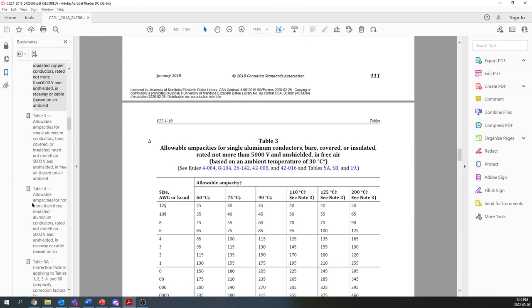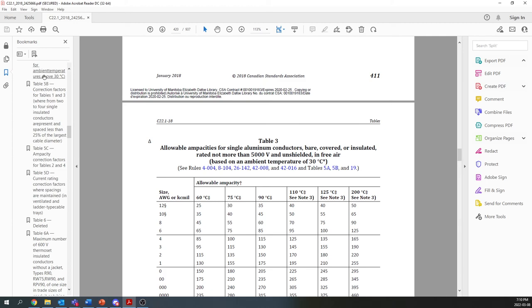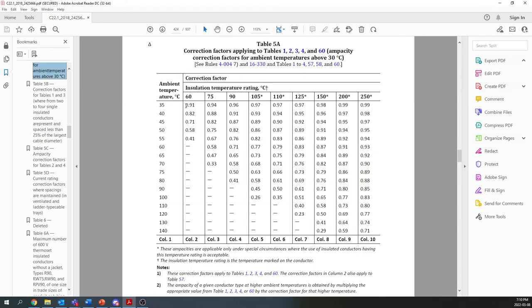But we have to take a look. Now we have to consider our correction factors. First is the ambient temperature. I said that we are looking at a 40 degree ambient. This is one case where you can actually use the 90 that's in those conductor temperatures. Not all conductors are 90 degrees. Some of them are 75, or even old ones might be 60 that you might see around. And often when a conductor gets wet, it's derated to either 60 or 75. But in general, we're using 90 degrees. This is a dry situation. At 40 degrees, we have to apply a 0.91 insulation correction factor.